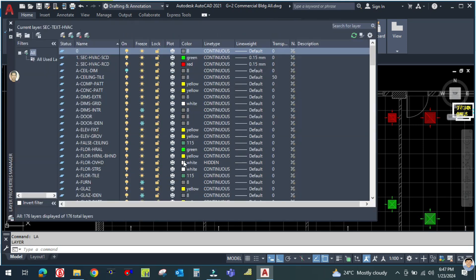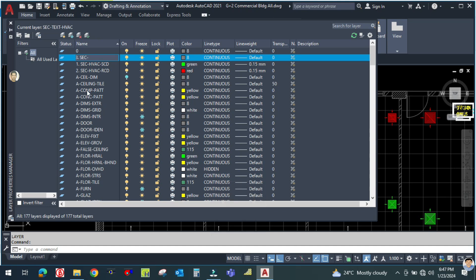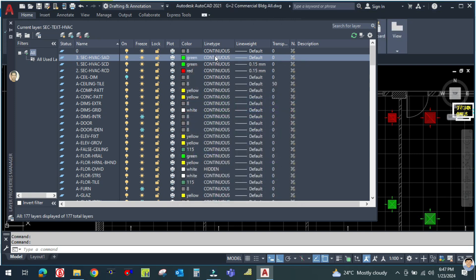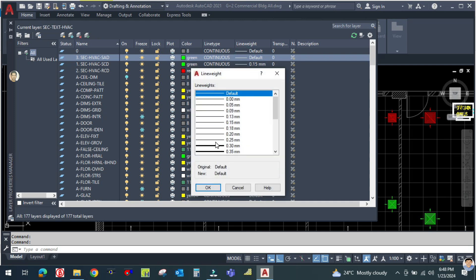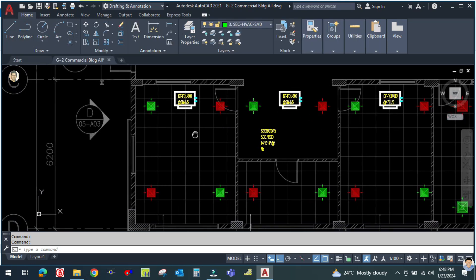First, create a new layer. Type 'la' to open the layer manager, then create a new layer. Name it layer number three: HVAC supply duct. Select a color for the supply duct and click OK. Set the line type to continuous and the line weight to 0.3. Double-click to make this the current layer.